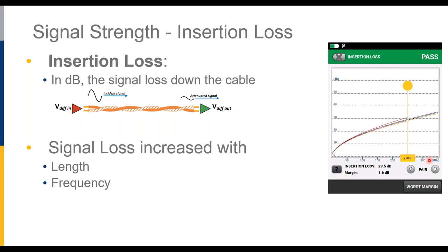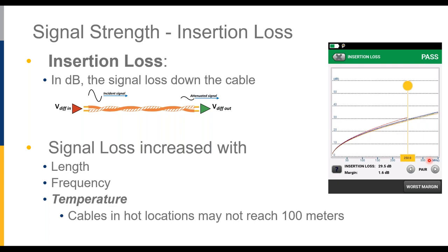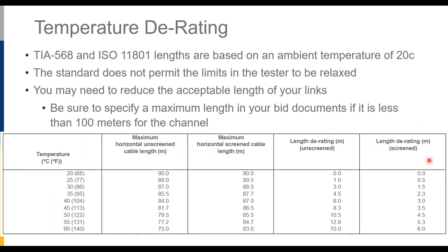Something that kicks in especially in industrial environments: signal loss also increases with temperature. The 100-meter maximum is contemplated at room temperature — 68°F — and as temperatures get higher, you need to derate or reduce the cable length to compensate for additional insertion loss. One real example: cabling tested fine, the oven was turned on, and there seemed to be a cabling problem. The oven had to be turned off to get close and test again. Make sure you know what temperature the cable is going to operate at.